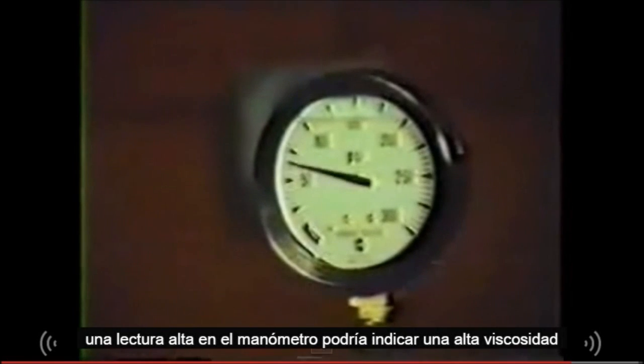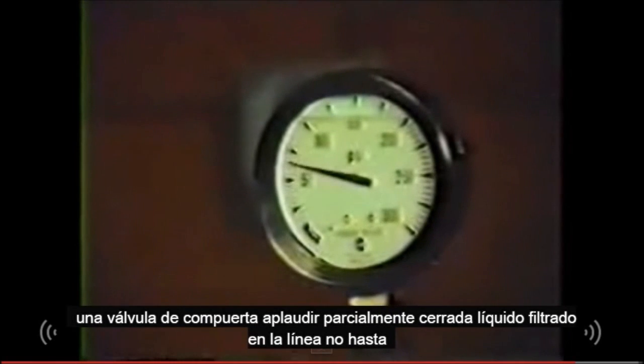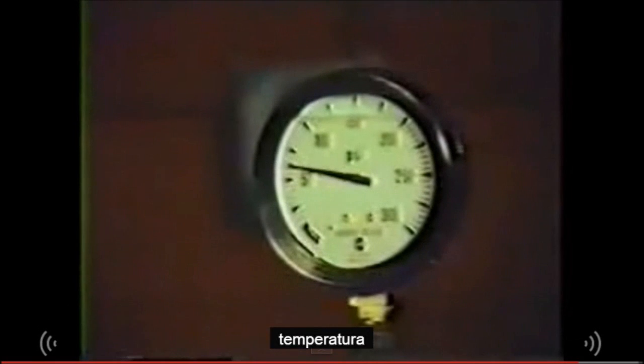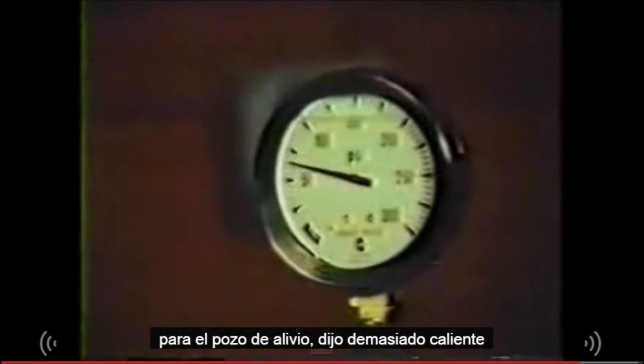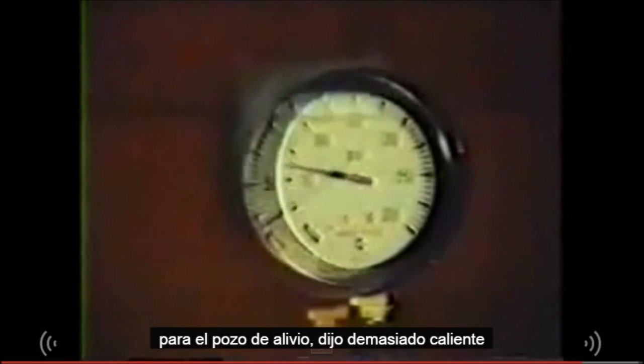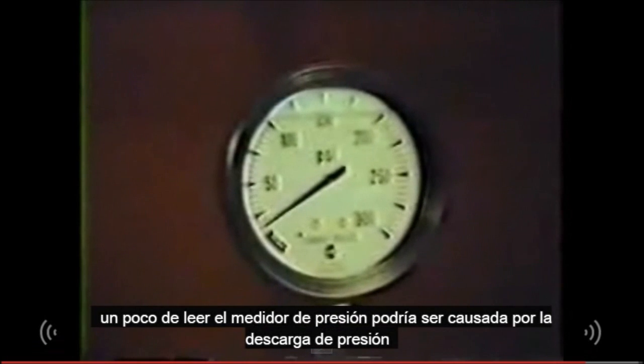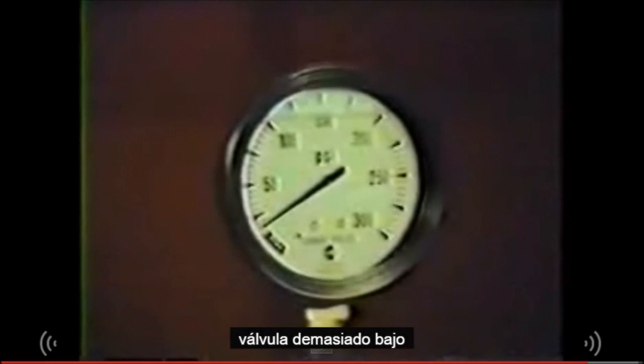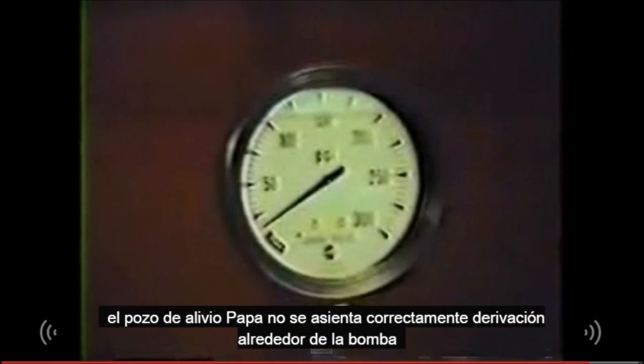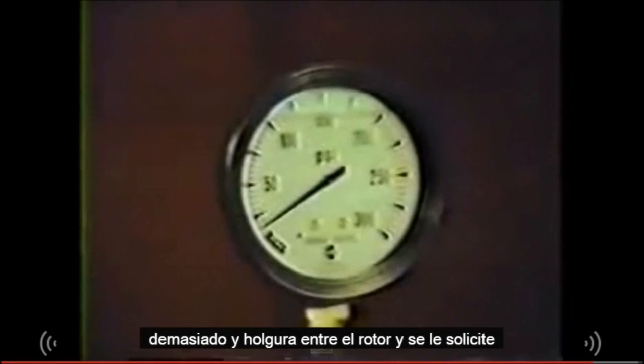A high reading on the pressure gauge might indicate high viscosity, a gate valve partially closed, a plugged filter, liquid in the line not up to temperature, or the relief valve set too high. A low reading of the pressure gauge could be caused by the pressure relief valve set too low, the relief valve poppet not seating properly, the bypass around the pump partially open, too much end clearance between the rotor and pump head, or a worn pump.